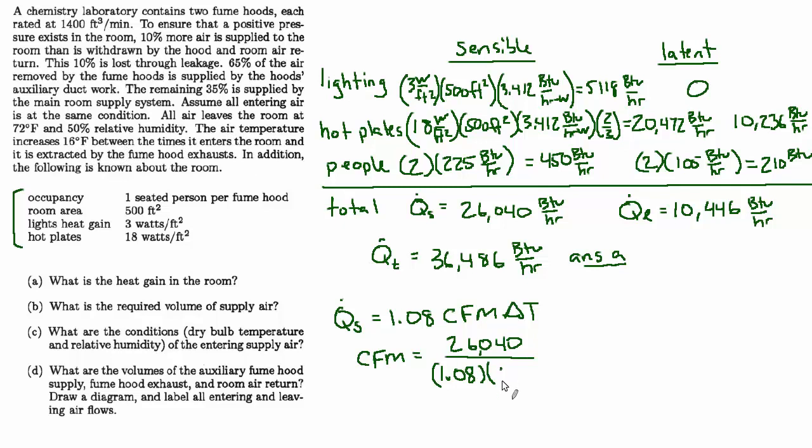And that gives us a volume flow rate of 1,507 CFM. So that's the required volume of supply air, answer B.